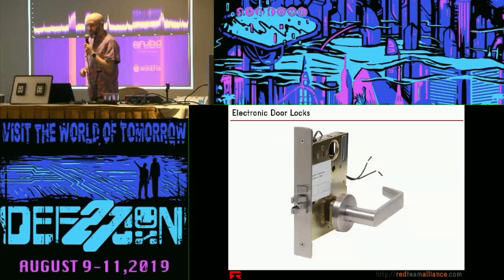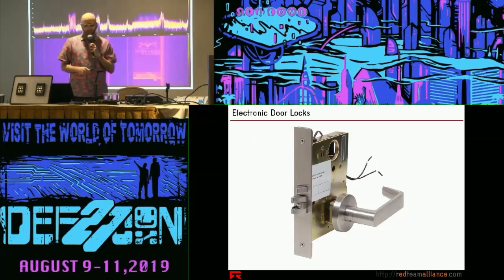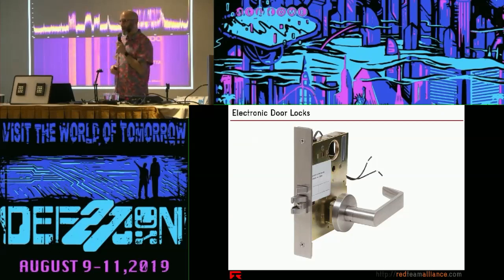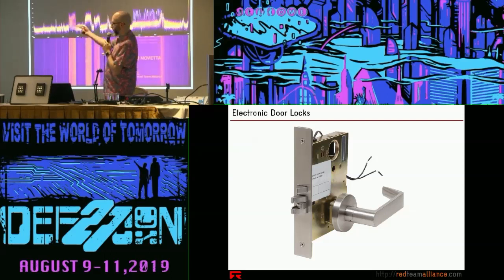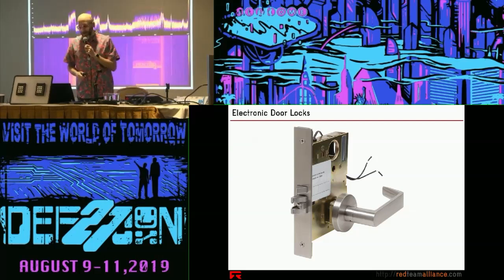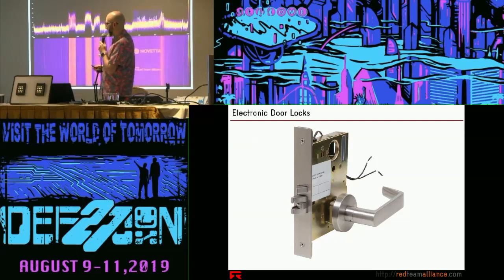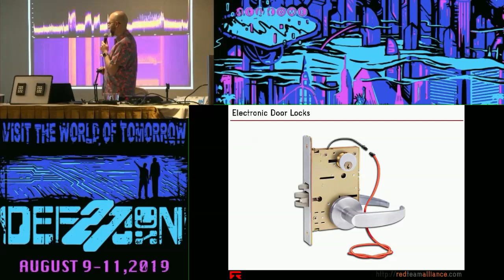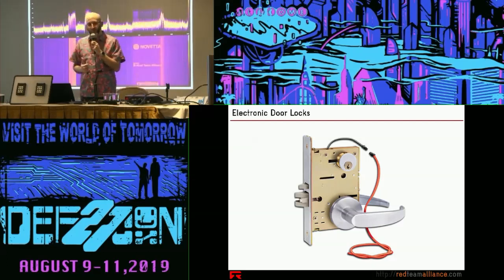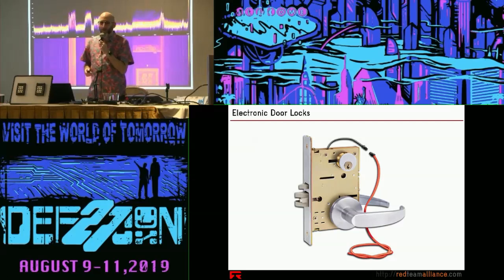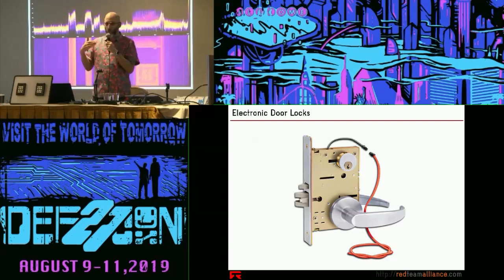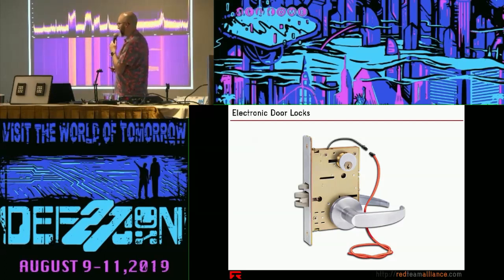The third kind is an electrified lock set. This does not use an electrified strike or a magnetic lock plate, but rather has a solenoid hidden inside the lock itself. In all of these cases, what's happening is you have a source of power — whether that be a transformer, AC or otherwise, and a backup battery — powering these secure entry and exit devices, whether they be mag locks or electrified strikes.